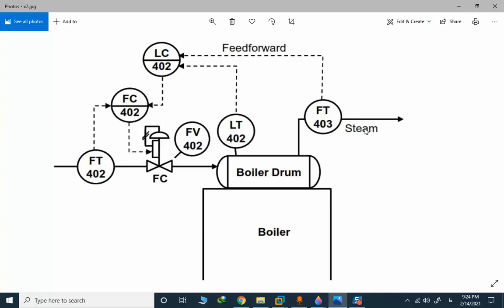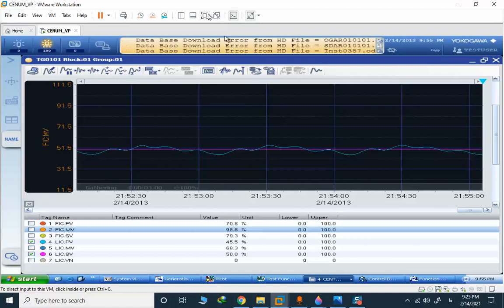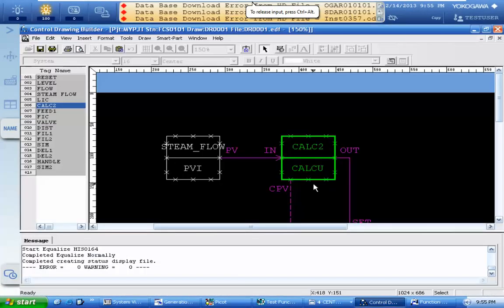In this simulation I created some alternating behavior for the steam flow. In order to simulate the level of the boiler drum I use a combination of the feed water and the amount of steam used in the plant, and the steam is somehow oscillatory. The feedforward control is implemented in CentumVP based on the available documentation.